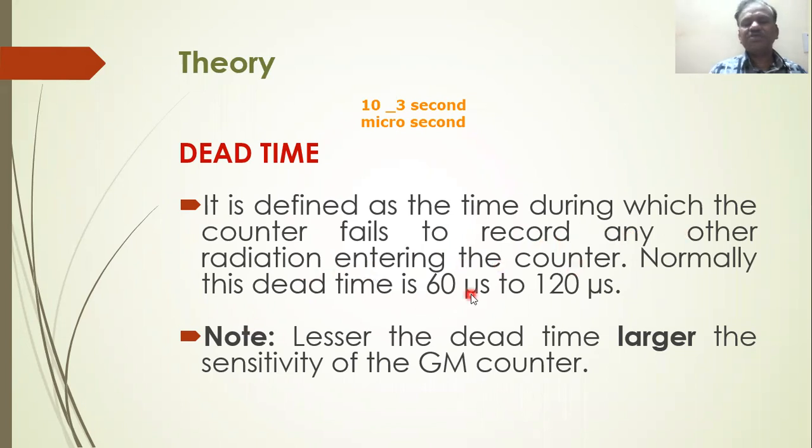Normally, the dead time is in terms of microseconds. Your detector is completely insensitive during this time. Very important: the lesser the dead time, the larger the sensitivity of the instrument. The sensitivity is said to be more if the dead time is lesser.